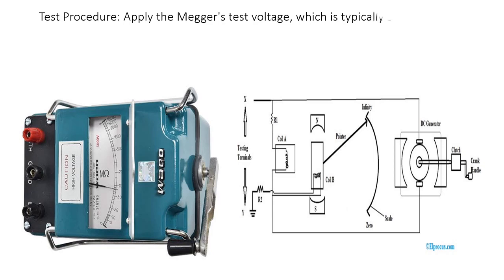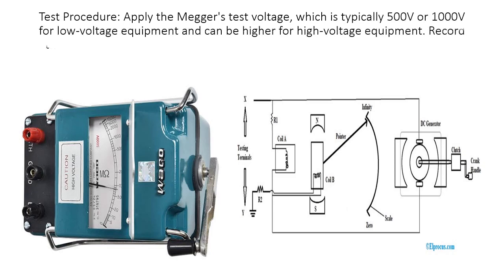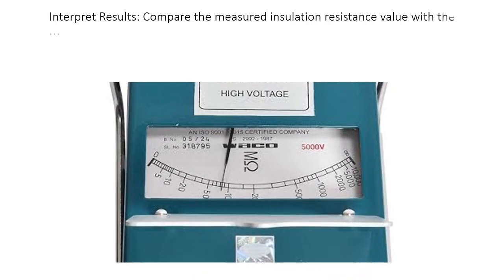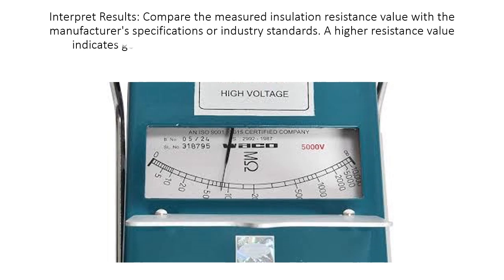Test Procedure: Apply the Megger's test voltage, which is typically 500V or 1000V for low voltage equipment and can be higher for high voltage equipment. Record the insulation resistance value displayed on the Megger after the test stabilizes, usually after one minute.